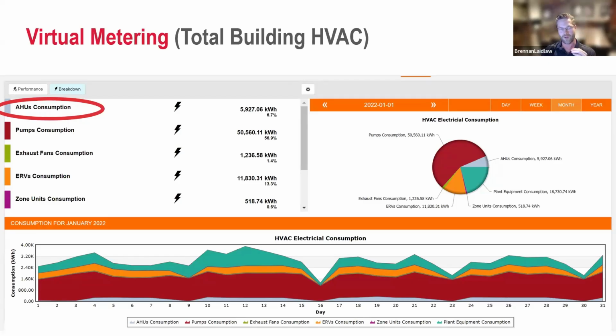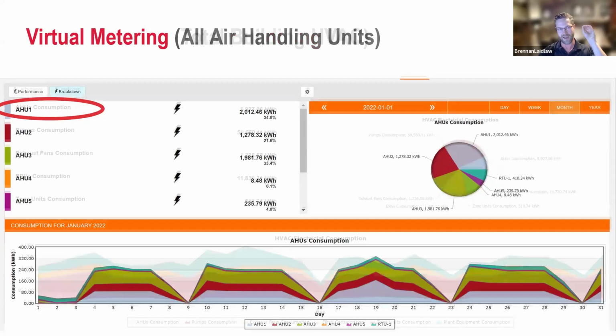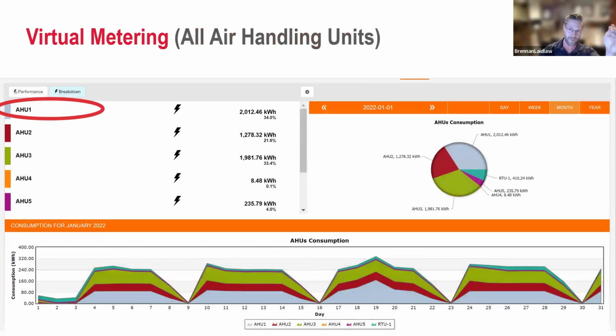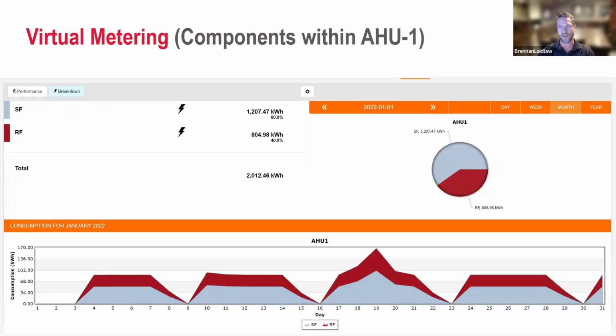So we were able to give a totalized view of the amount of energy being used in the building, which was used as an ongoing commissioning tool just to see all the individual components. So this would be a total building view, which you can drive into like, hey, I want to see how much of my air handling units are using for energy. Then here's all your different air handling units. And you can even drill down inside the air handling unit and say, oh, this specific fan is using this much energy. So it's a way for you to turn all of your motors and basically all your equipment into energy meters without actually installing an energy meter, just using programming and proper calculations on energy. So very good use case.